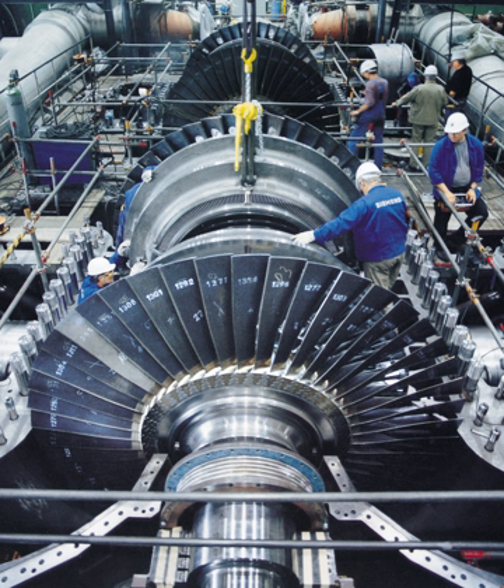So in power systems where generation is distant from the load, it is desirable to step up (increase) the voltage of power at the generation point and then step down (decrease) the voltage near the load. Secondly, it is often more economical to install turbines that produce higher voltages than would be used by most appliances, so the ability to easily transform voltages means this mismatch between voltages can be easily managed.